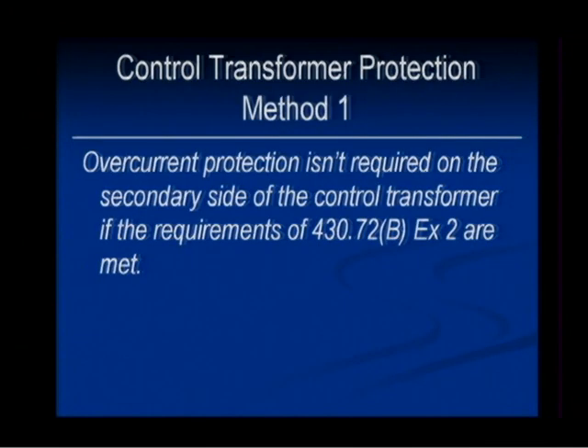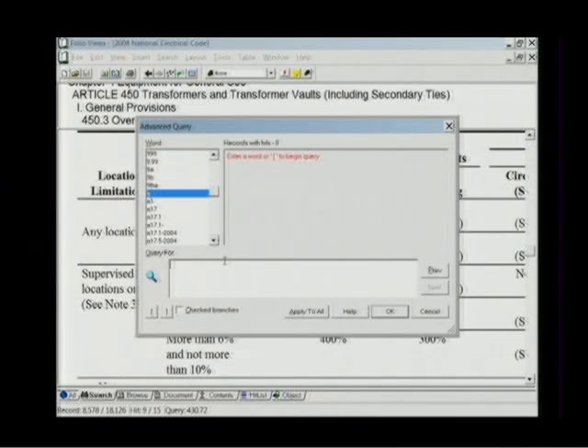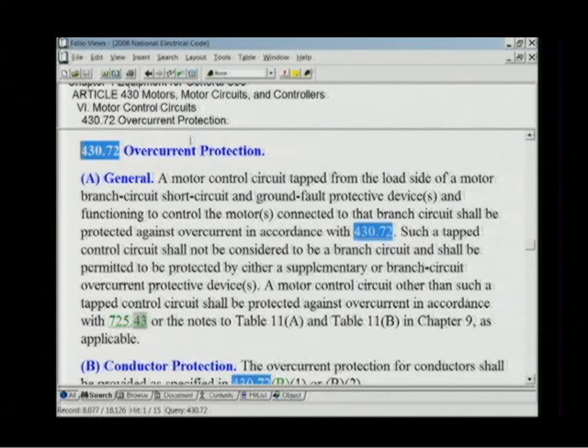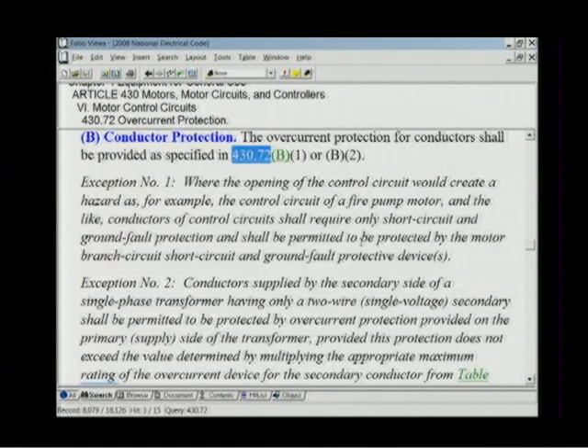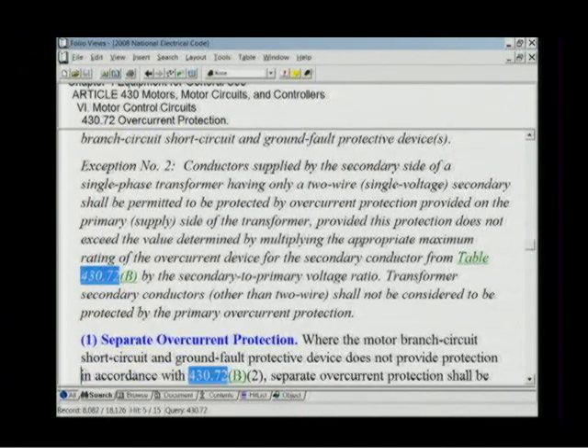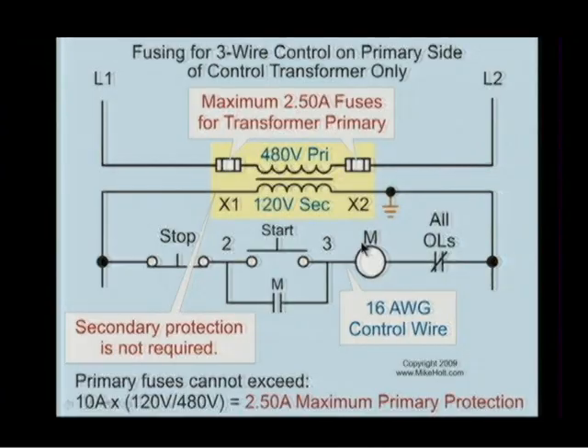Let's go with method number 1. Overcurrent protection isn't required on the secondary side of a control transformer if the requirements of 430.72(B) Exception 2 are met. Well, let's go back to 430.72(B) Exception 2. Conductors supplied by the secondary side of a single-phase transformer having only a 2-wire single-phase secondary shall be permitted to be protected by overcurrent protection provided on the primary side. I'm not going to get into any more details than that.